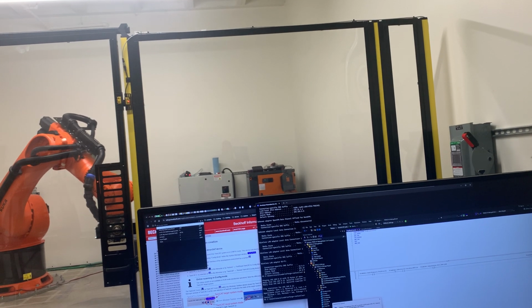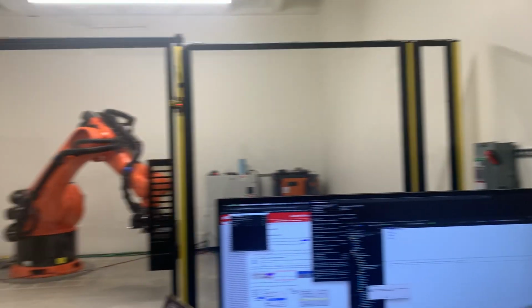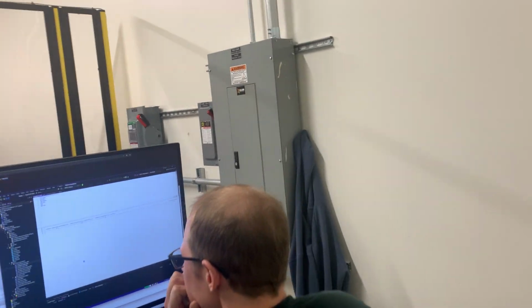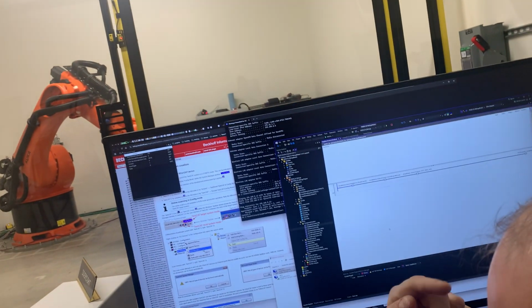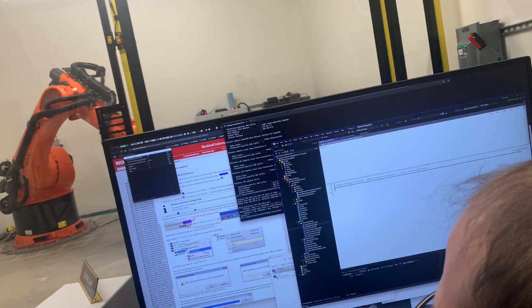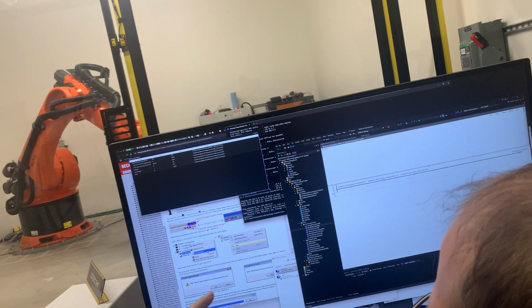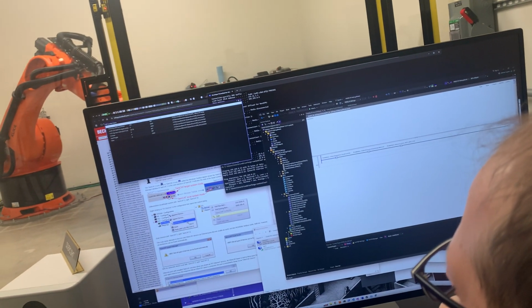It's asking you if you want to create a port for you to be able to see what's going on with the PLC. Say yes. That's fine. Confirm the changes. Because we downloaded some code, it flipped back, and I'll push new code. But whenever you log in with download, it's not in run mode anymore, so you have to hit that green button to turn it back in run mode. And now you can see the state.